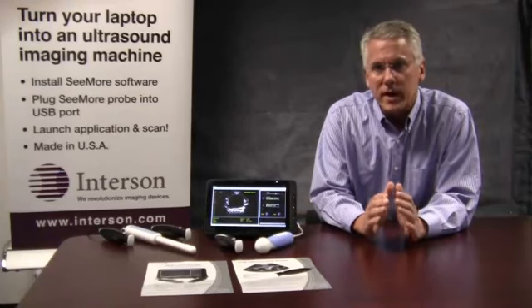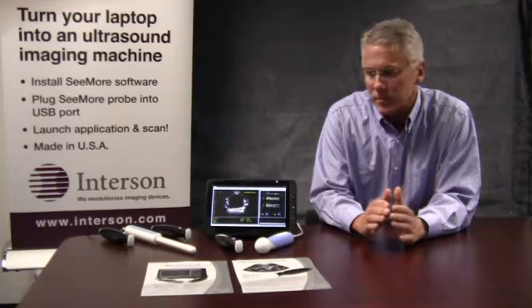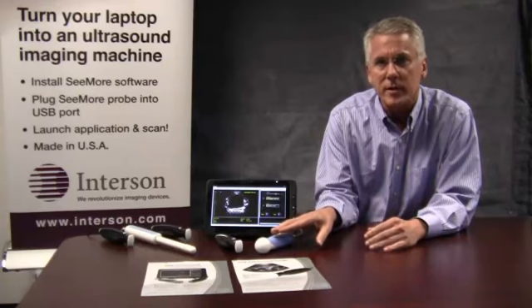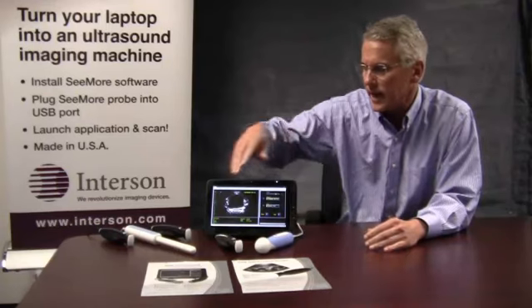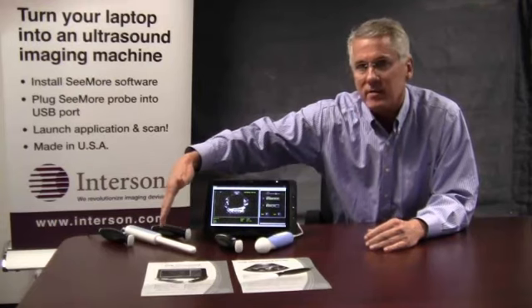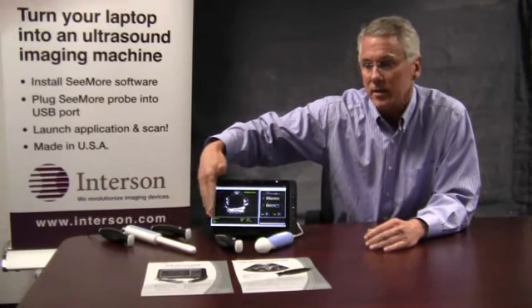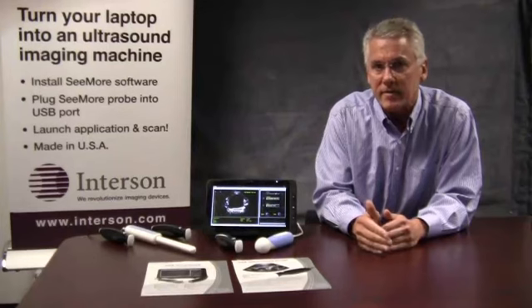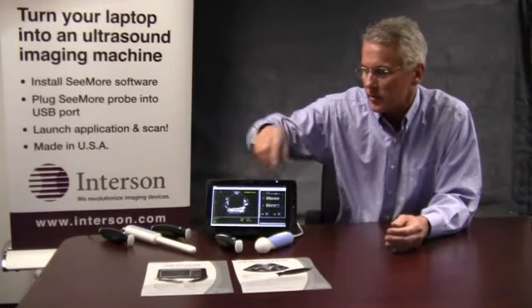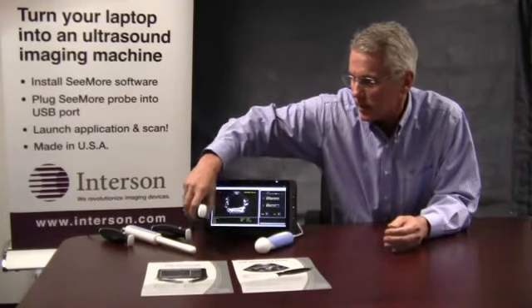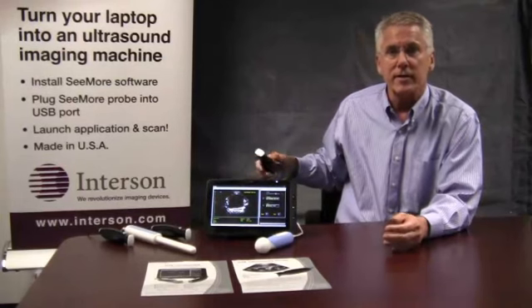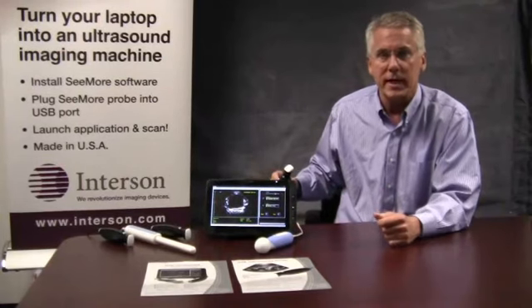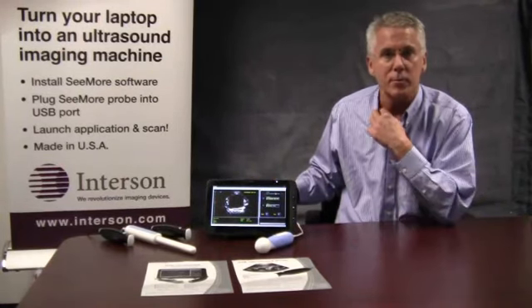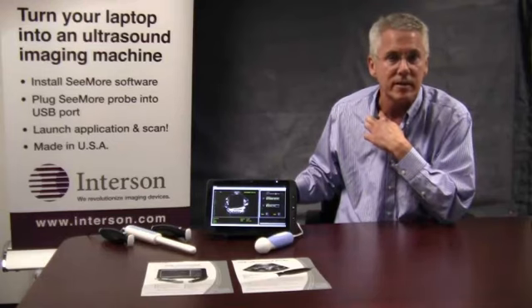The other probes cover a different focal zone. As we said, this one covers 4 centimeters to 20 centimeters. I'd like to now cover these 3 probes in here because they all have the same focal zone. The focal zone on these is 0.5 centimeters to 4 centimeters. So they work very nicely to cover things that are at a shorter depth than what the abdominal probe can handle.